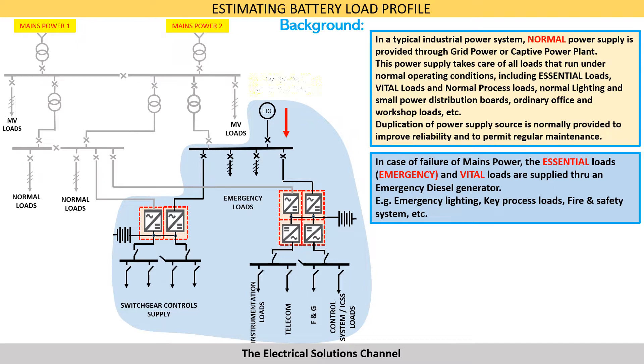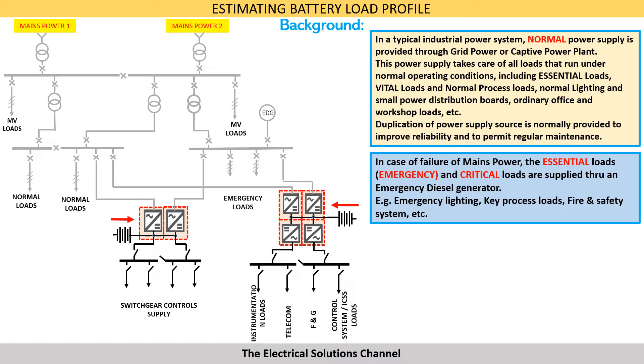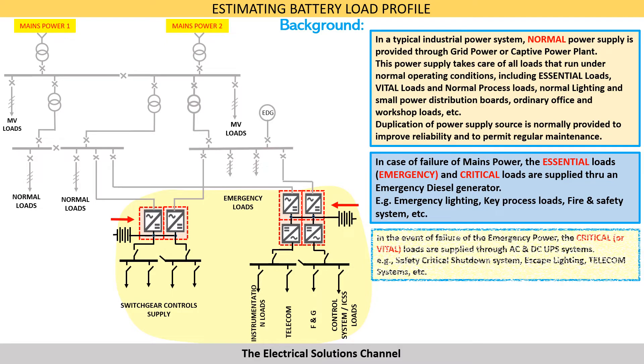In case of failure of mains power, the essential loads or emergency loads and vital loads are supplied through an emergency diesel generator. Some examples of these loads are emergency lighting, key process loads, fire and safety systems. In the event of failure of emergency power, the critical or vital loads are supplied through an AC or DC UPS system — for example, safety critical shutdown systems, escape lighting, and telecom systems.